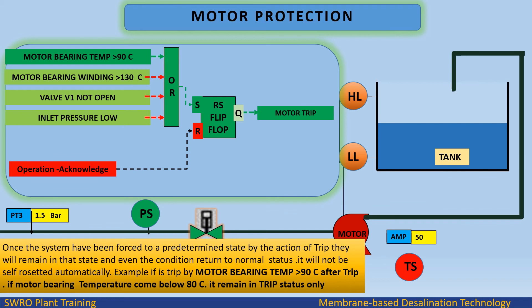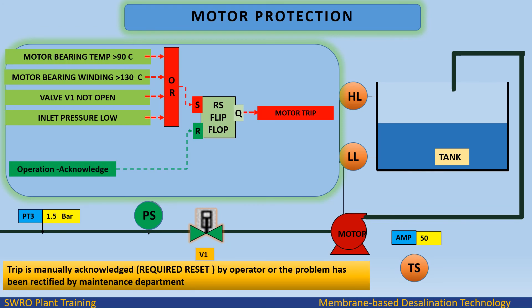For example, if a trip is caused by motor bearing temperature greater than 90 degrees, and after the trip the bearing temperature comes below 80 degrees, the system remains in trip status. The trip must be manually acknowledged and reset by the operator, or the problem must be rectified by the maintenance department.